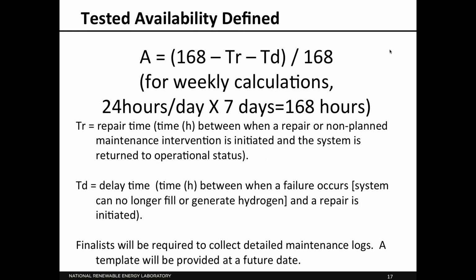How we calculate availability: it's calculated on a weekly basis, so 168 hours available in a week. We'll subtract off any repair time measured in hours, and we're defining repair time as the time between when a repair or maintenance intervention is initiated and when the system is returned to operational status. So even if there isn't technically a repair with somebody going out with wrenches, but you have to manually go and reset something, that's going to count as repair time.